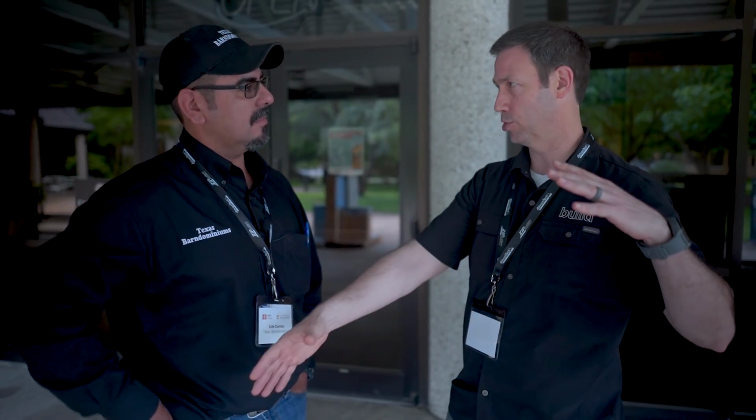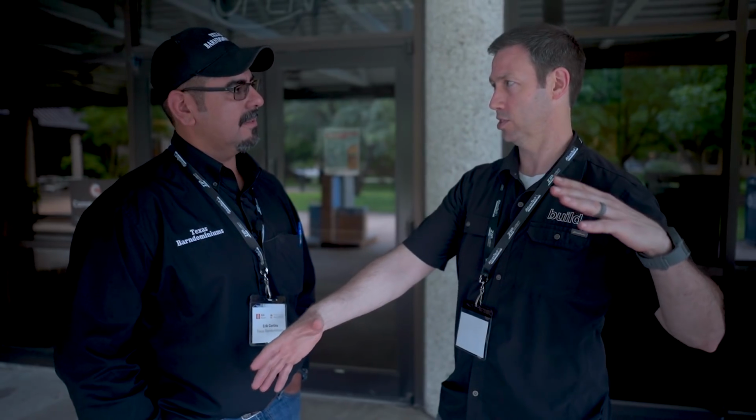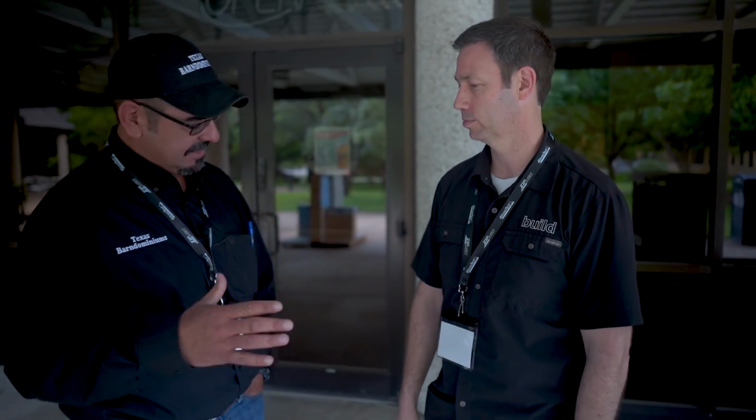And sometimes it'll run so the coil gets cold enough and you've got all that air on your coil, all that wetness on your coil, but then the machine turns off because it's satisfied the temp. The coil's all wet, and what happens? The blower still runs on there, so it rehumidifies all that air, and you never lost any humidity. Until the first drop of condensate drops down the drain, there's no dehumidification that's happening. Right, it's still there, contained. Still there. Yep.